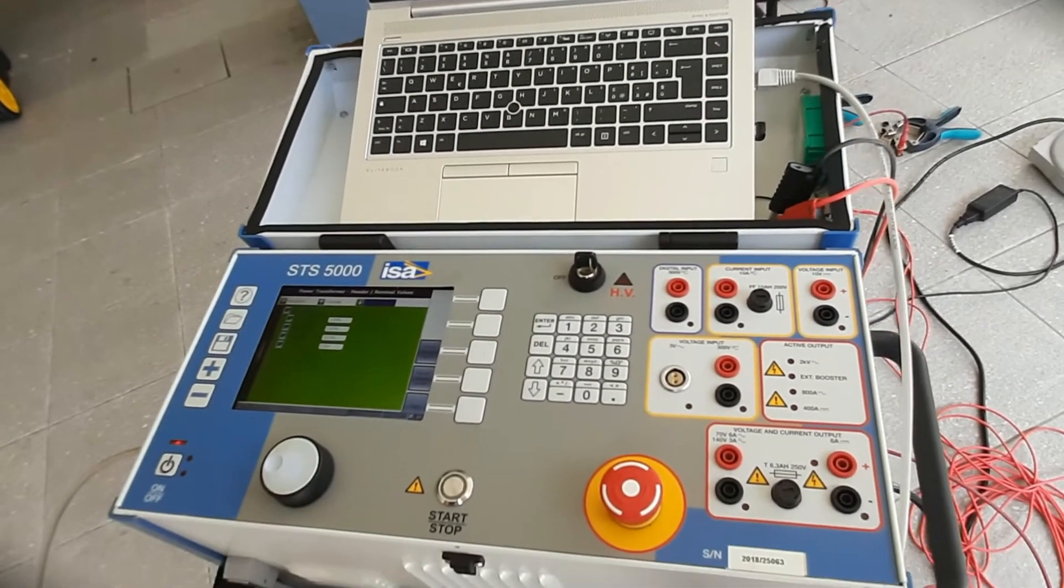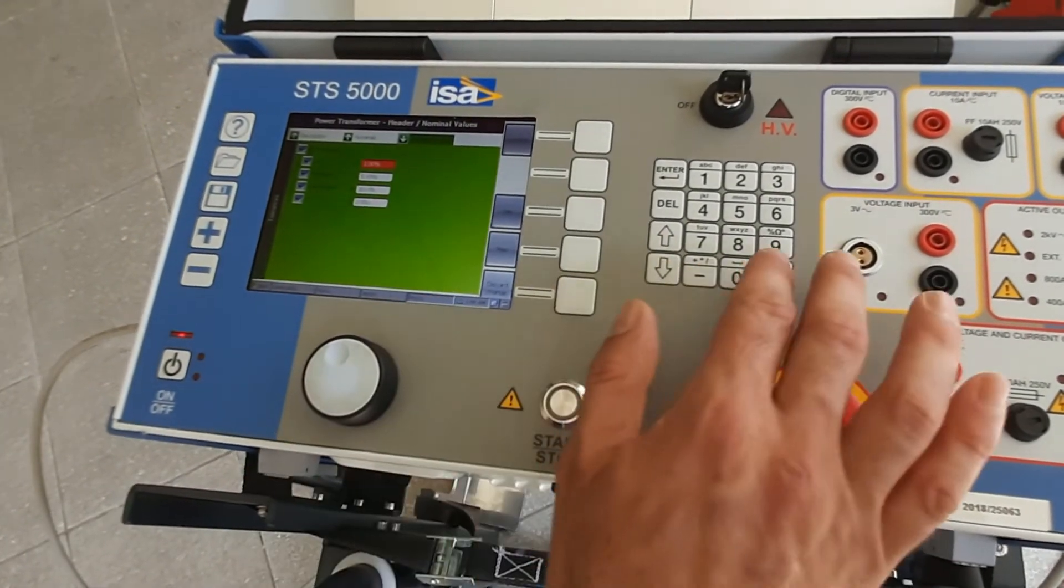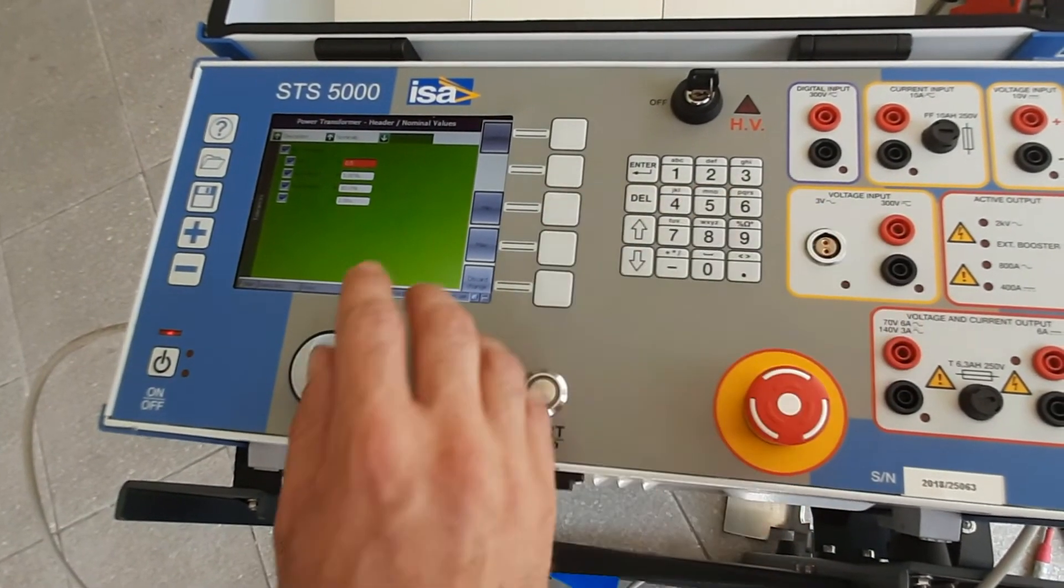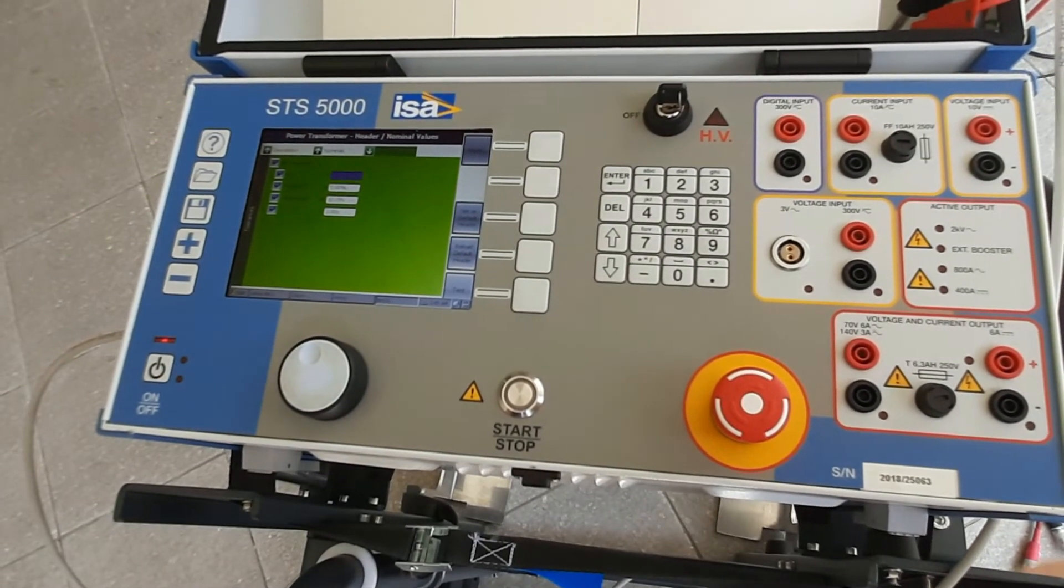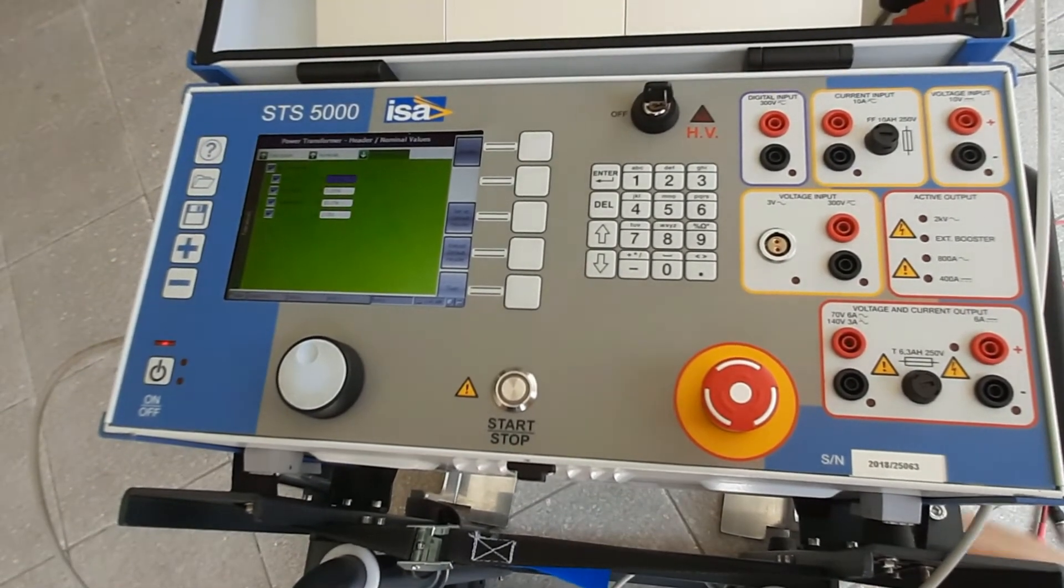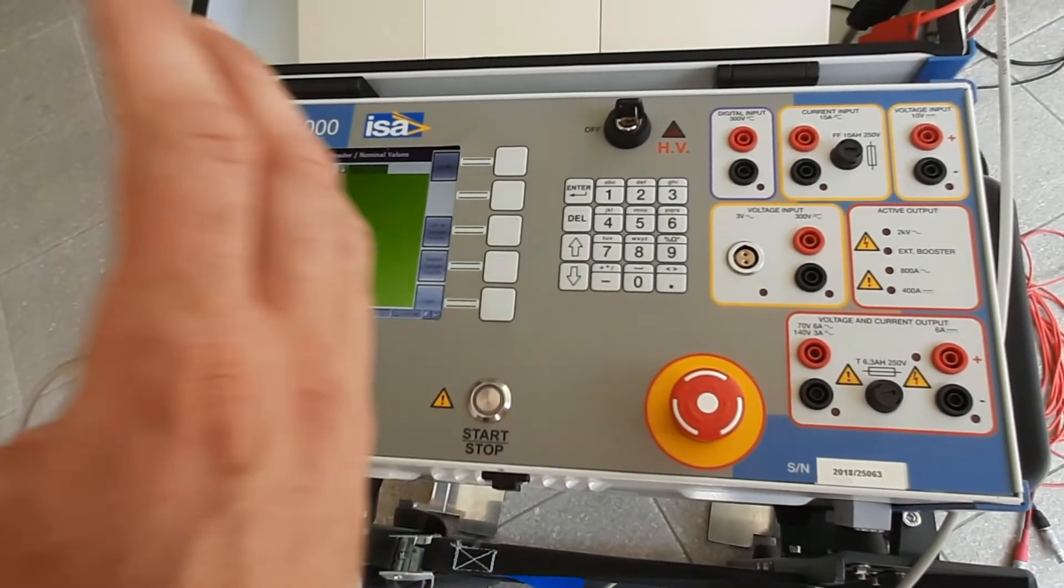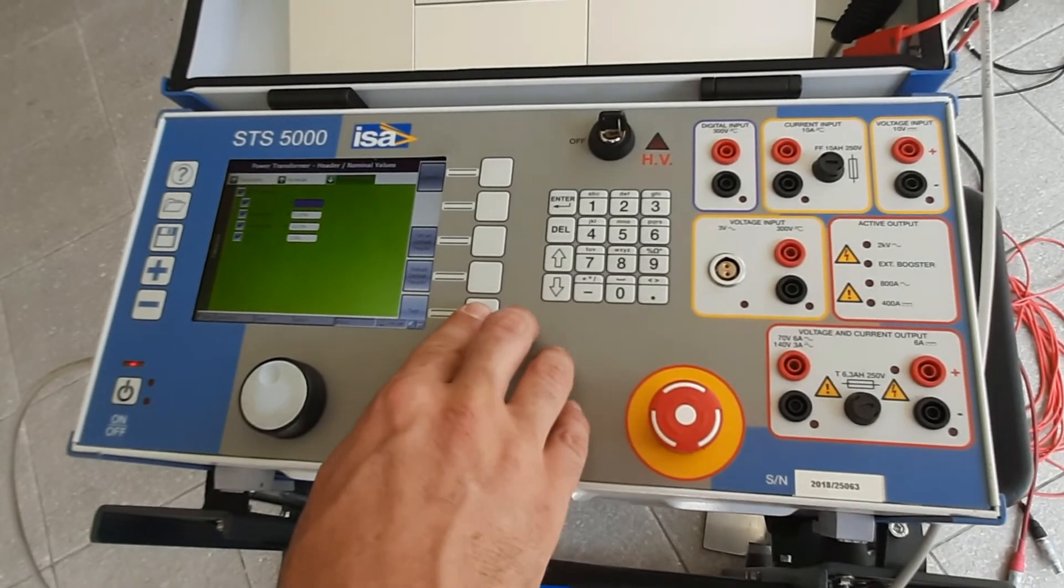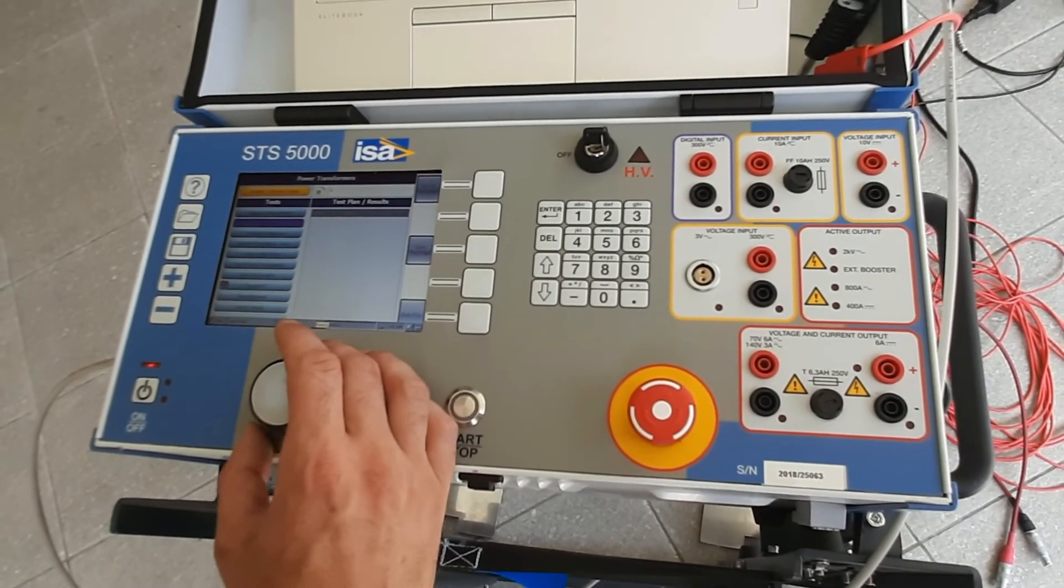So now, since all this is done, we can also show you one more thing which is tolerances. Here we're going to change this ratio to 0.5 percent because this is more or less a magical number in standards for the ratio test. If the difference is more than 0.5 percent, then it's a bad result. That transformer needs to be looked at. I press the programmable button test and then I move on to ratio.